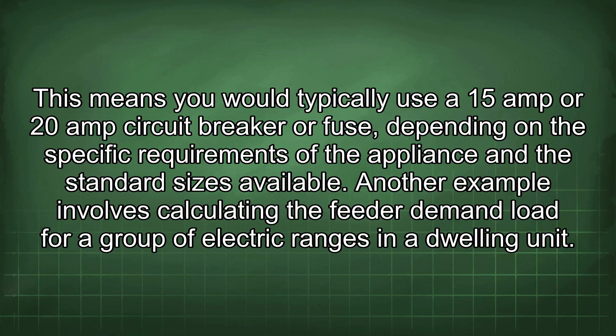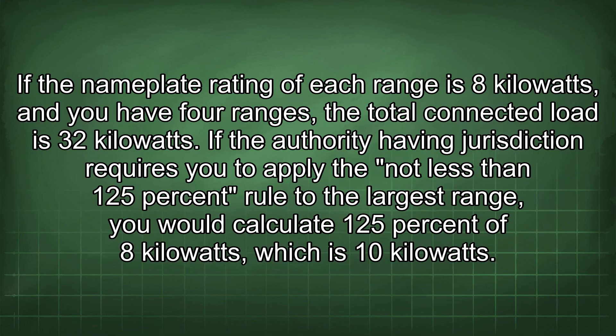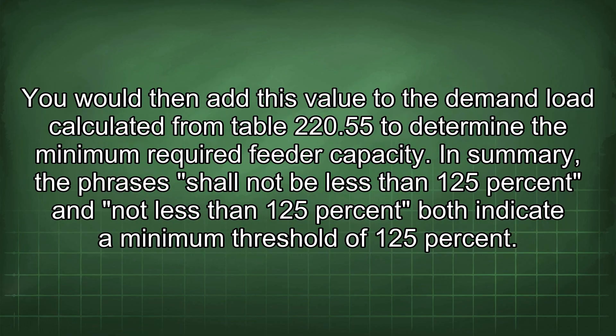This means you would typically use a 15 amp or 20 amp circuit breaker or fuse, depending on the specific requirements and standard sizes available. Another example involves calculating the feeder demand load for a group of electric ranges in a dwelling unit. The NEC provides tables such as table 220.55 that allow you to apply demand factors to the total connected load. If the nameplate rating of each range is 8 kW and you have 4 ranges, the total connected load is 32 kW. If required to apply the not-less-than-125% rule to the largest range, calculate 125% of 8 kW = 10 kW, then add this to the demand load from table 220.55 to determine the minimum required feeder capacity.